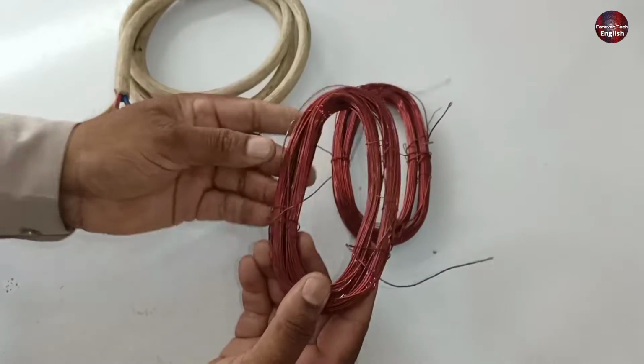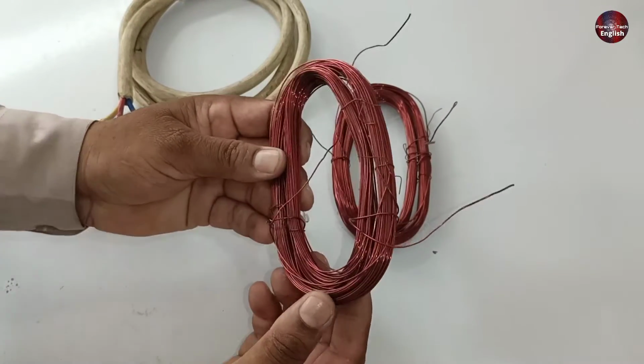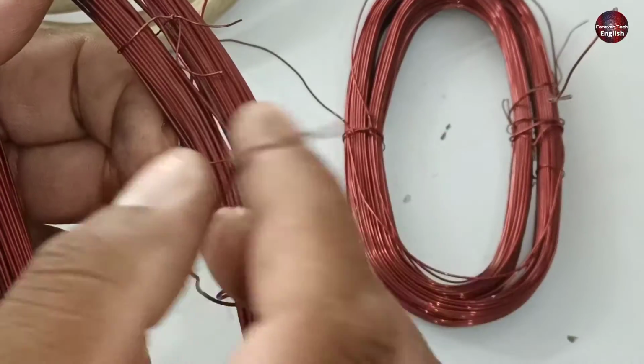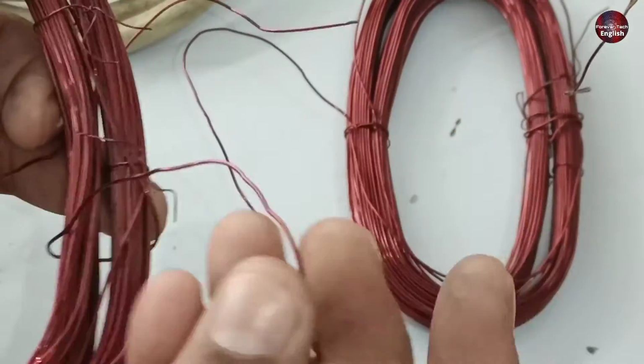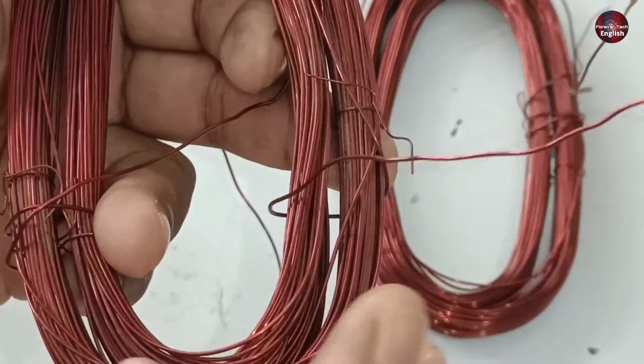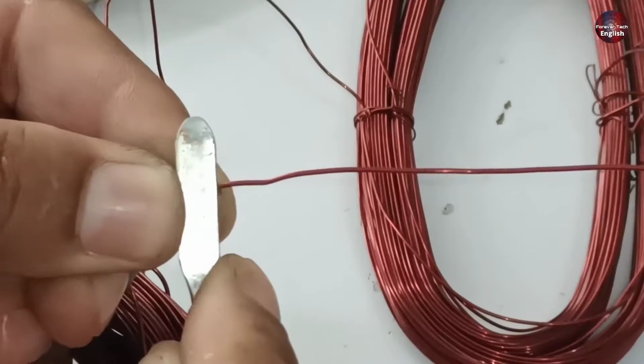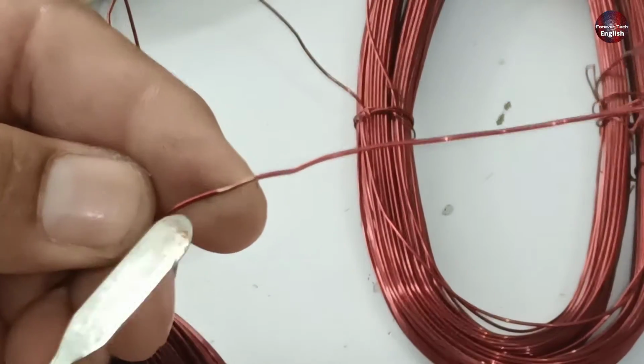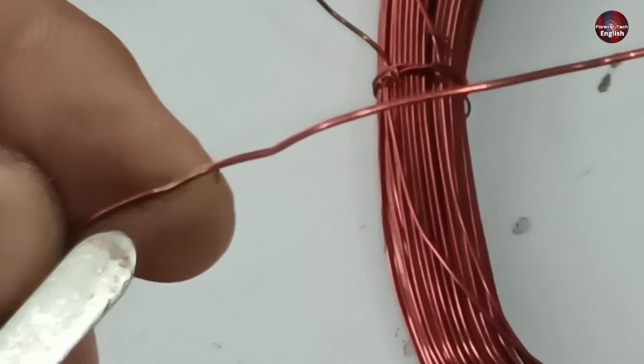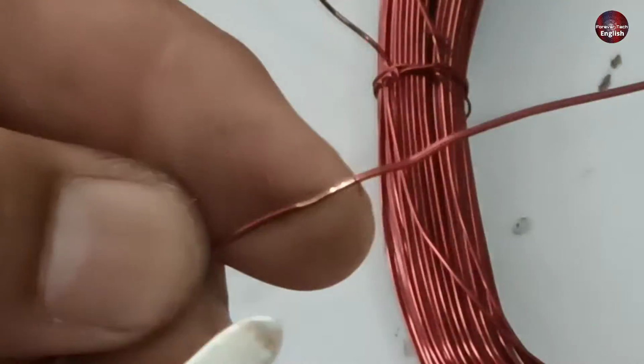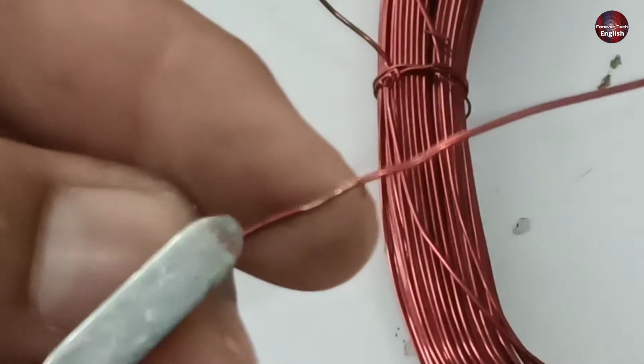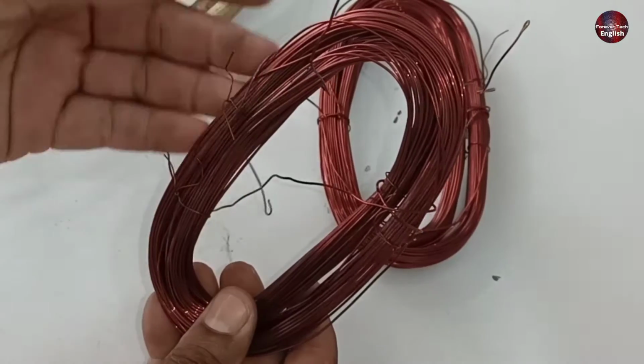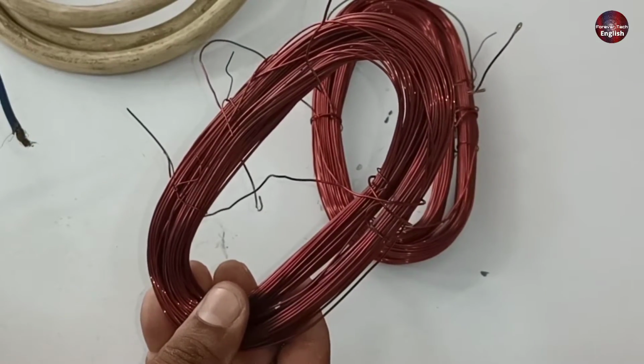So see these coils, as the compressor also has coils wound inside it. These wires also have an insulation layer. Now let me show you the insulation layer on these wires. See, you can see the wire beneath the insulation. The insulation on this wire is quite thin. And this is what we check, as I have told you before. Now I will check the insulation resistance of these wires.